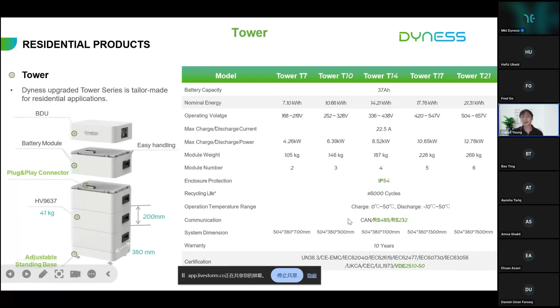Upon this BDU we can see the ports here, same as the previous Dyness battery. For the parallel settings, we have to do the wiring from the BDU box, also known as the control box. In a paralleling situation there's communication, positive and negative sockets, and the power button. On the other side of this BDU there is a DC breaker.